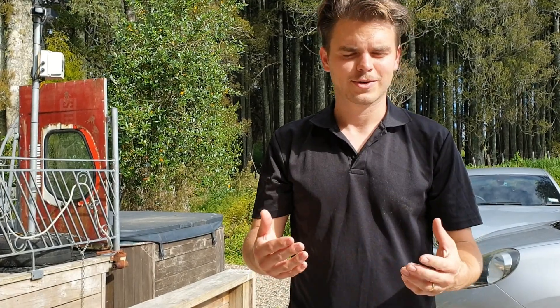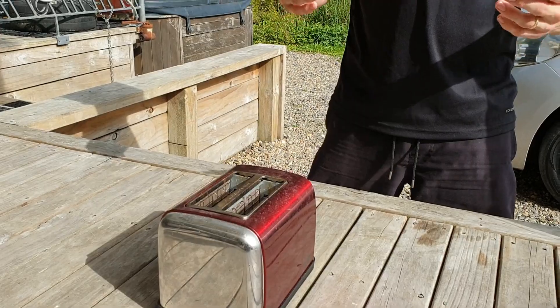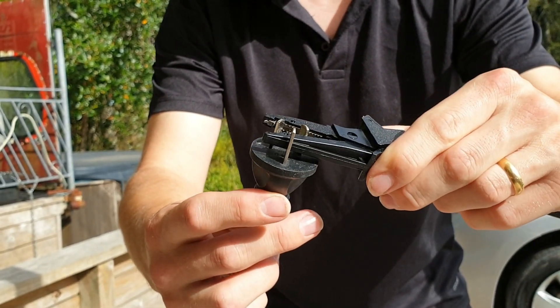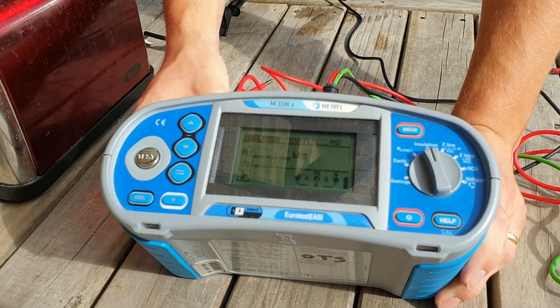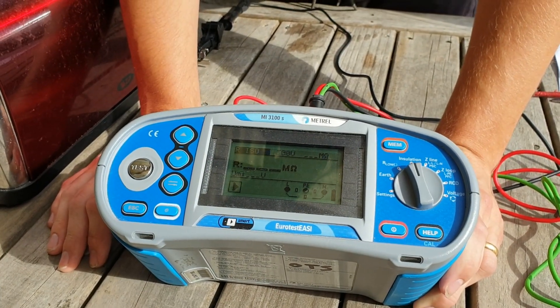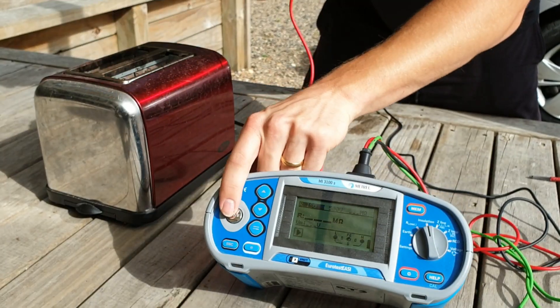Now that our earthing conductor test has passed and we know there's a good earth from this point to all the metal parts on the body, we're going to do an insulation test. The test result must not be less than 1 megaohm for an appliance. We take our plug and connect the prongs across phase and neutral, then switch our meter to insulation resistance test — this is set to 500V. However, if your appliance has electronics inside, it's recommended to set it to 250V DC. We then test on all the metal parts.